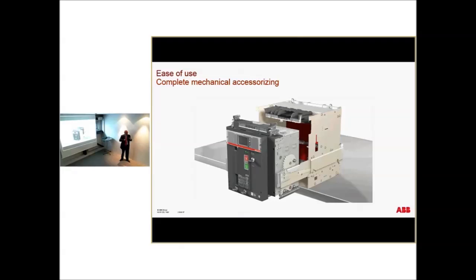So you have something in the plant, and somebody says, okay, the breaker has to be in open position, has to be locked. Nobody can touch except for the plant manager. Okay, I need to put an accessory. How can I do it? No problem. You remove things. The locks remain like it is for safety, if somebody else wants to check, and you put all the accessories.